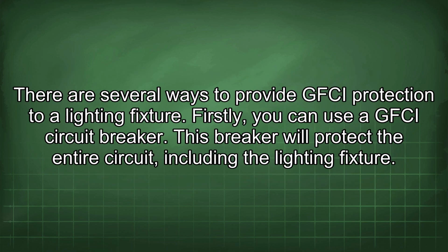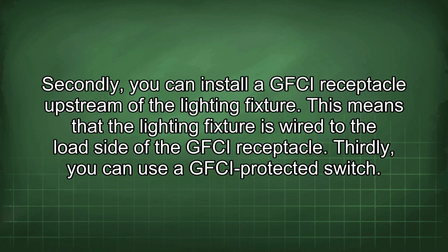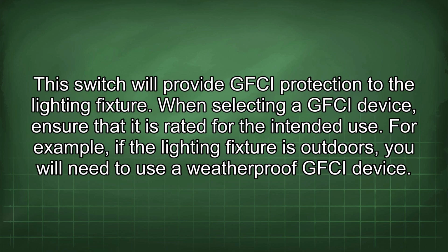There are several ways to provide GFCI protection to a lighting fixture. Firstly, you can use a GFCI circuit breaker. This breaker will protect the entire circuit, including the lighting fixture. Secondly, you can install a GFCI receptacle upstream of the lighting fixture. This means that the lighting fixture is wired to the load side of the GFCI receptacle. Thirdly, you can use a GFCI protected switch. This switch will provide GFCI protection to the lighting fixture.